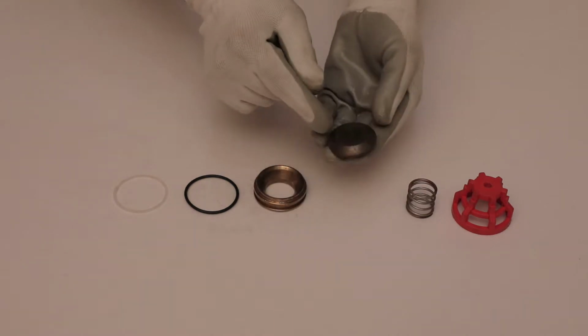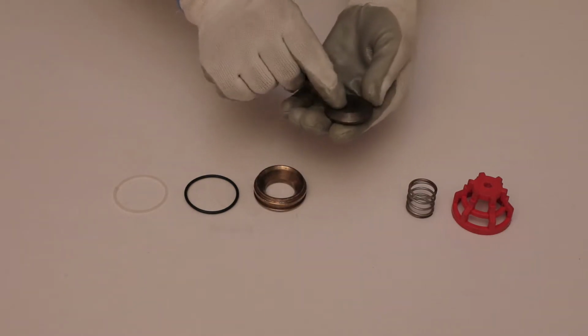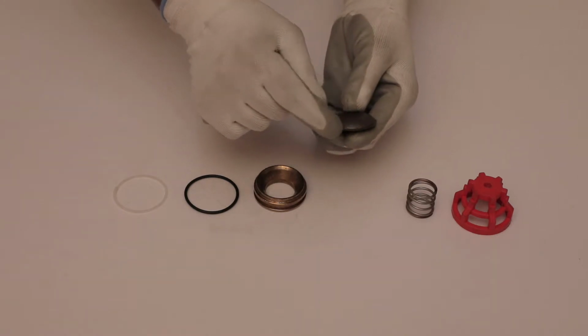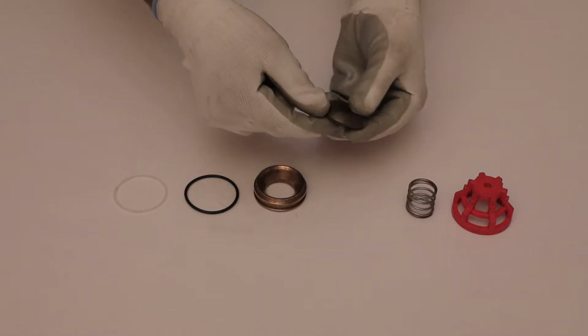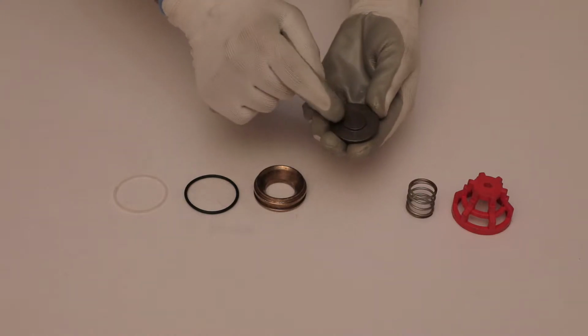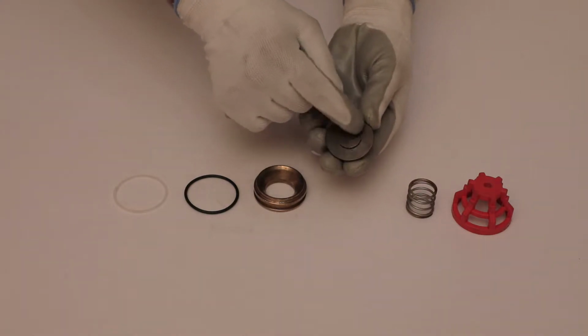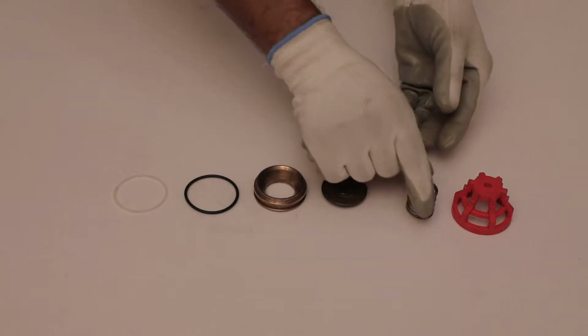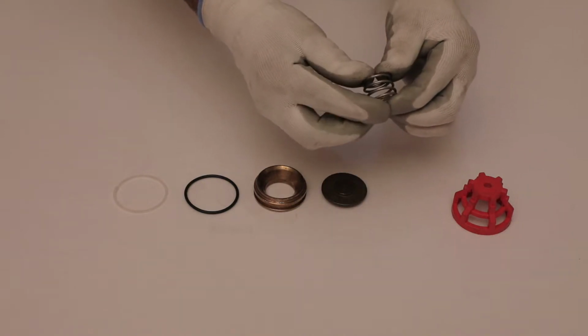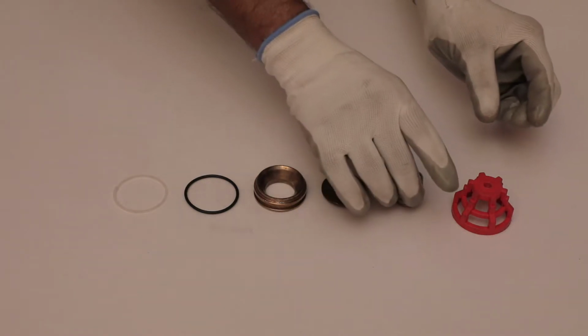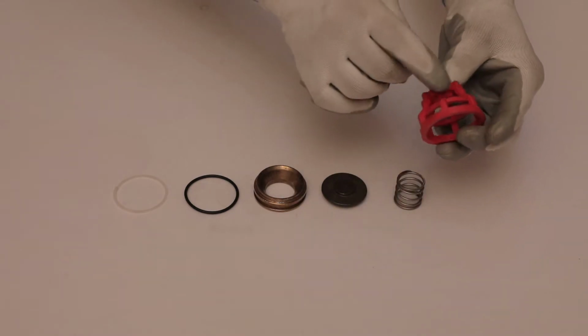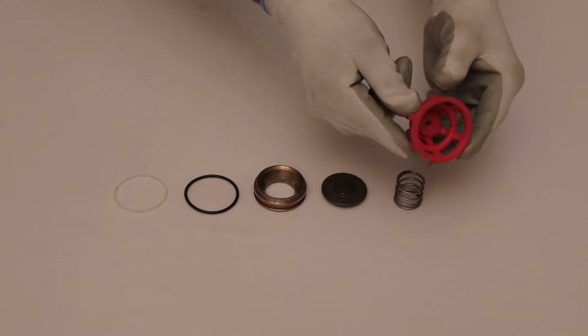Inspect the surface of the suction and discharge valve plate for any wear or dent marks. Check helical spring for stiffness and damage. At last, inspect the suction and discharge valve guide for any damage.